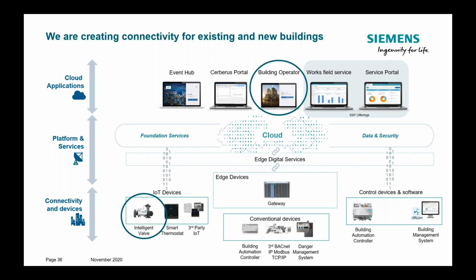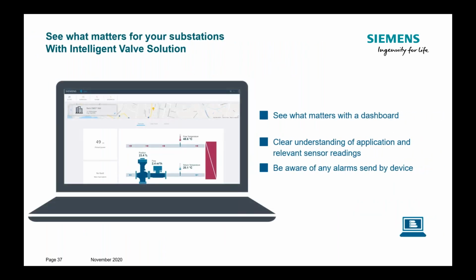For intelligent solutions, the interesting thing on these cloud solutions is clearly that you are online connected to these devices on the distribution level. With a dashboard, you can see what matters. You can see the current power consumption. You can clearly see alarms which are coming from this device, if a sensor is broken or if it's not capable to transmit the right power because somehow the distribution network does not provide the right temperature levels and so on. So there you have the capability for monitoring the system.